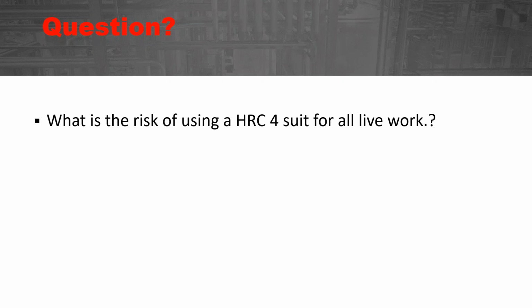All right, so a lot of companies for several years, if their employees do not wear daily arc-rated clothing, or some people still call it FR clothing, then what some companies have done is they have one duffel bag with category 2 clothing and equipment, and those coveralls would be good for category 1 or 2. And they have another bag that is category 4. And then they would use that bag, the arc flash suit and the beekeeper type hood in that, if it's category 3 or 4.